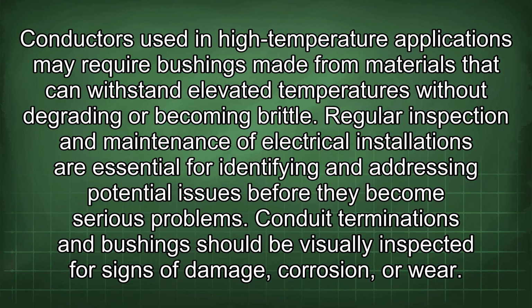Regular inspection and maintenance of electrical installations are essential for identifying and addressing potential issues before they become serious problems. Conduit terminations and bushings should be visually inspected for signs of damage, corrosion, or wear.